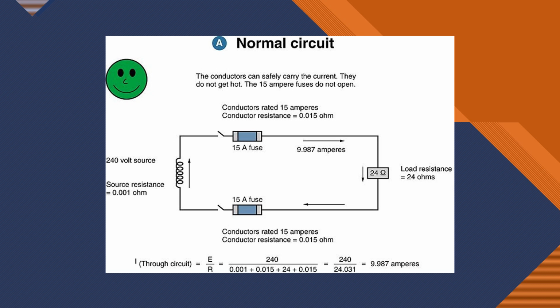If I have a 240 volt source, I have a 24 ohm load. I also have the resistance of my conductors, and that's going to end up in a normal circuit condition, 9.987 amps. I put a 15 amp fuse. I could probably run 14 gauge wire on this and everything would be totally normal. Everything's great.